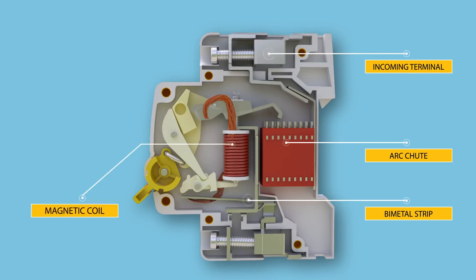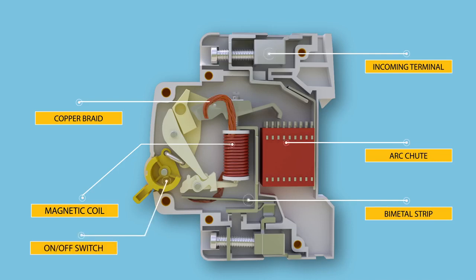The magnetic coil is part of the magnetic tripping arrangement, where in case of short circuit or heavy overloads, a strong magnetic field is produced in the coils. Copper braid connects the moving element with the static element. The on-off switch is the operator with which we manually interrupt or turn on the electric circuit. In the outgoing terminal, we connect the outgoing phase from the circuit breaker.